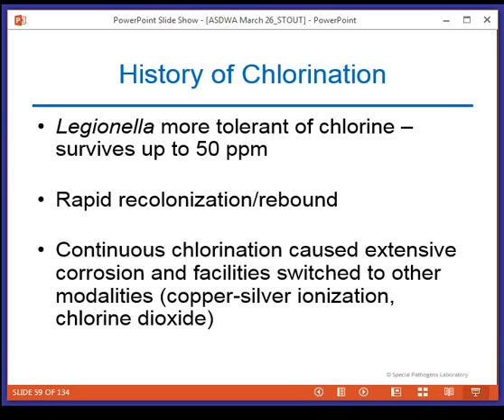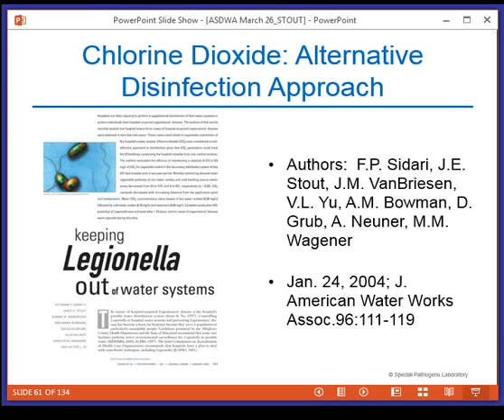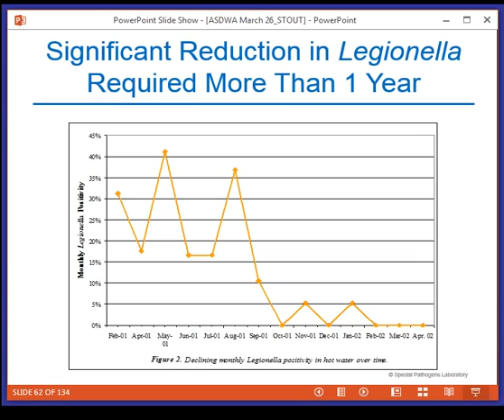So what have we learned about chlorine dioxide? Our first study was published in the American Water Works Association Journal in 2004. This was a hospital study in eastern Pennsylvania, and what they did was they put chlorine dioxide on the reservoir of the hospital. What this slide shows is when you apply chlorine dioxide to the cold water of a building or buildings, it takes a long time for Legionella positivity to be reduced. So this slide shows percent positivity over 30% at the early phase, and then almost a year later before it got down to below 10%.